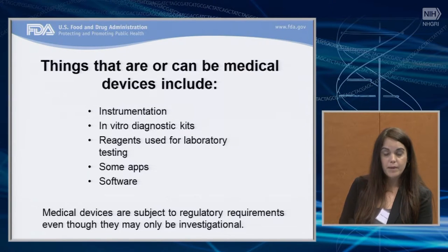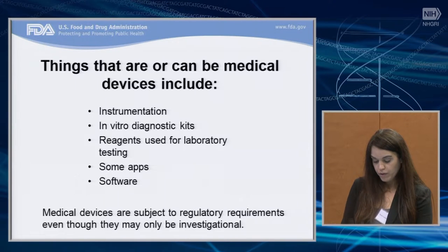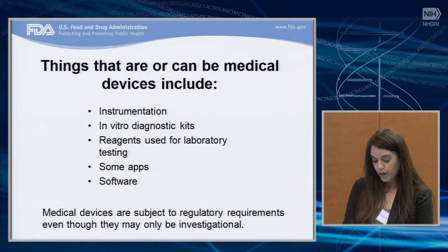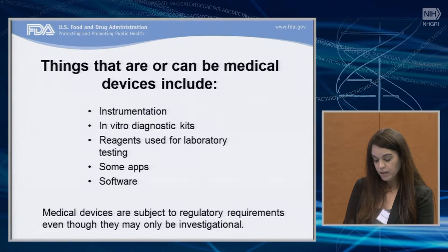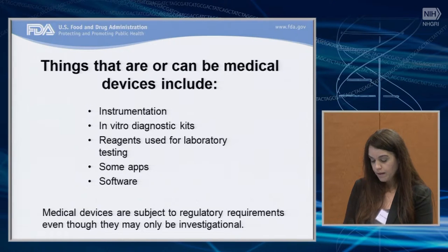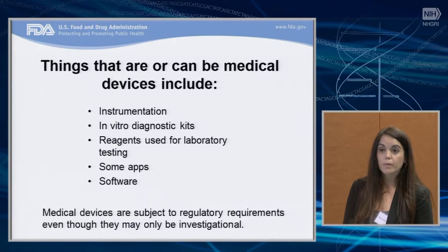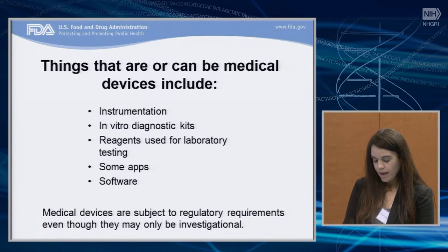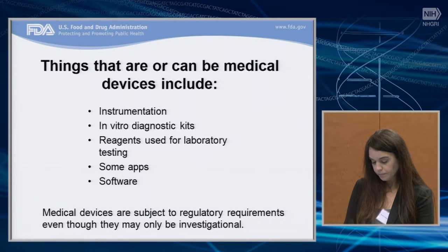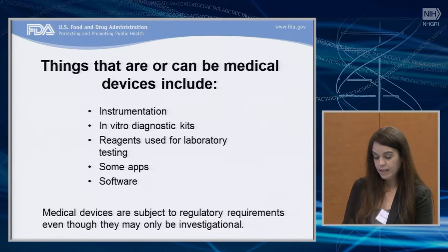Some examples of medical devices include instrumentation, in vitro diagnostic kits, reagents used for laboratory testing, and maybe some apps. Although we recognize that most apps would not be considered medical devices, depending on what they do, they could meet the definition of a medical device. For example, if someone develops an app that actually makes a diagnosis, then it would likely be a medical device. Software can also be a component of a medical device. Medical devices are subject to regulatory requirements, even though they may be only investigational.